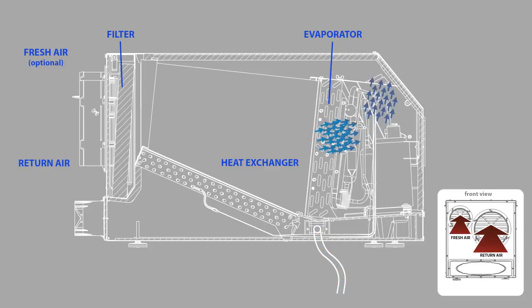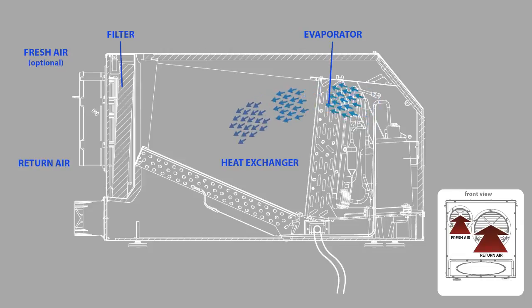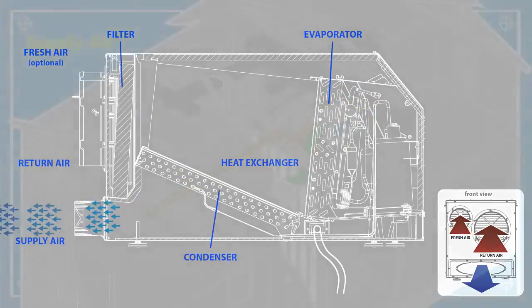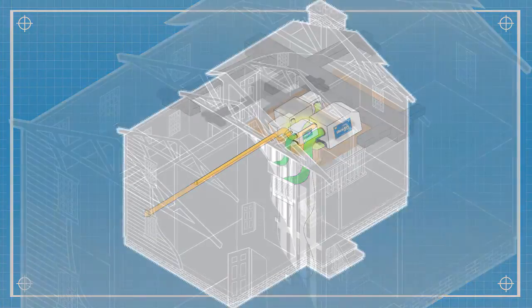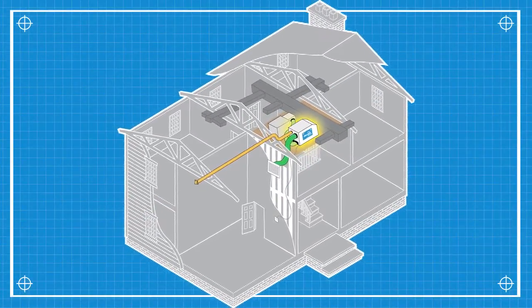The air then passes back through the heat exchanger and then through the condenser coils where it is slightly heated and delivered to the supply side of the HVAC system and distributed throughout the house. Fresh air supply ventilation systems, such as an UltraAir whole house ventilating dehumidifier, allow improved control and treatment of the air that enters the home. By slightly pressurizing the house, these systems dilute indoor pollutants and reduce the potential for backdrafting of combustion gases from fireplaces and appliances.